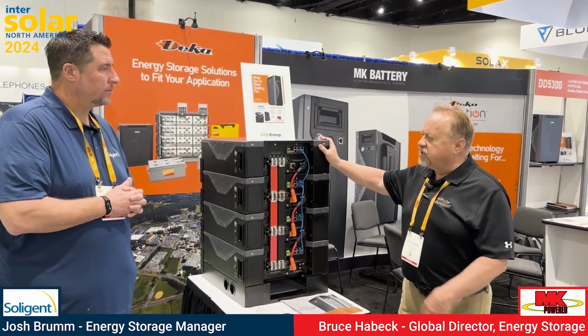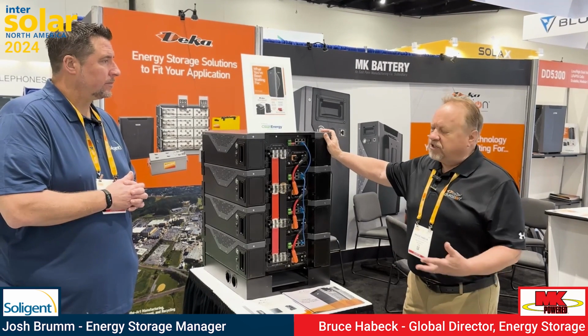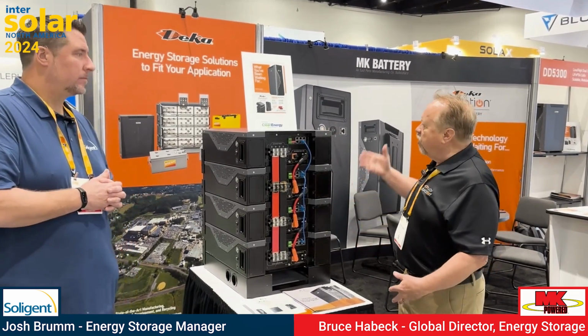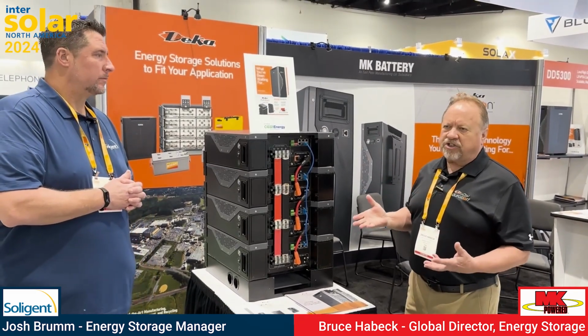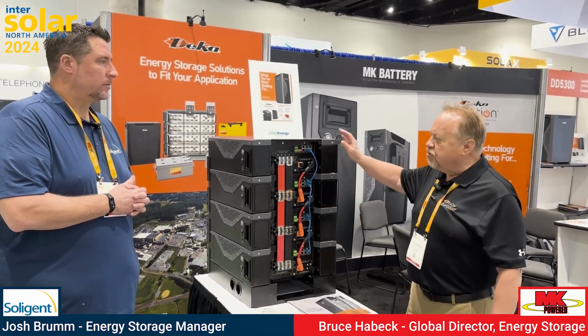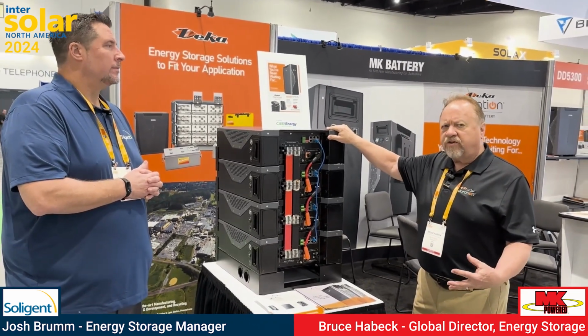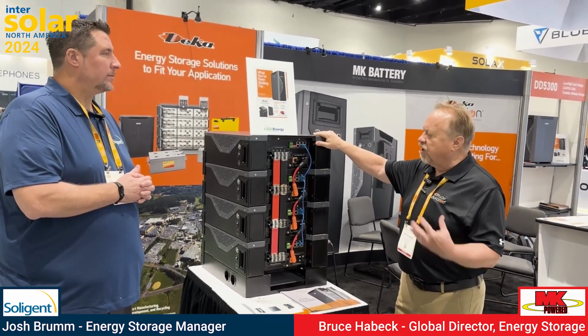These new chemistries are partial state of charge batteries, which is what you really need in most solar applications. In the real world, lead acid batteries were also in partial state of charge, and that's why they failed a lot more often: they ended up sulfating. When you use a true partial state of charge battery that has a BMS that makes sure it does get fully recovered and fully charged, that's what's really important.